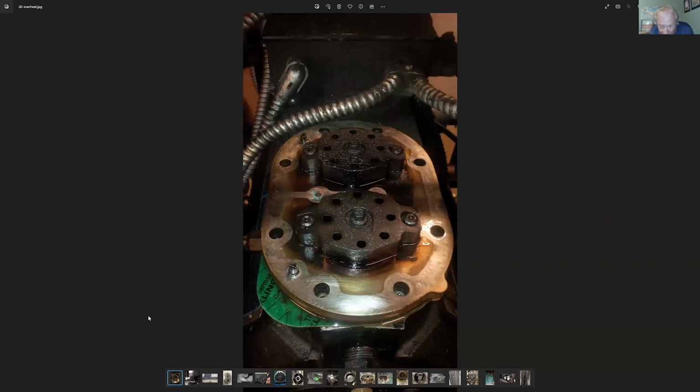Well, there's a good overheat there. It looks like, or is that contamination? Looks like you could wipe that clean, don't it? Yeah. It's just to take the time to look, and to be honest, it's going to take a lot of inspections. It's not that you look at one and all of a sudden you're always going to figure it out, because there's lots. I've inspected hundreds and hundreds of compressors, and there's some that I just didn't know.